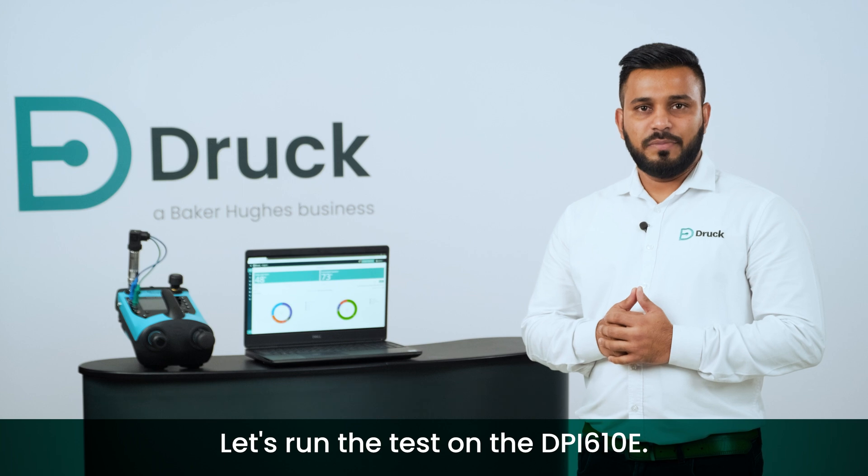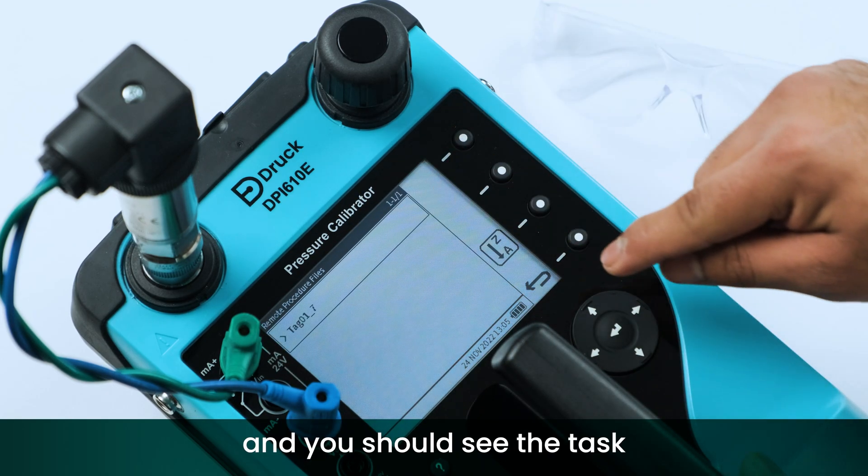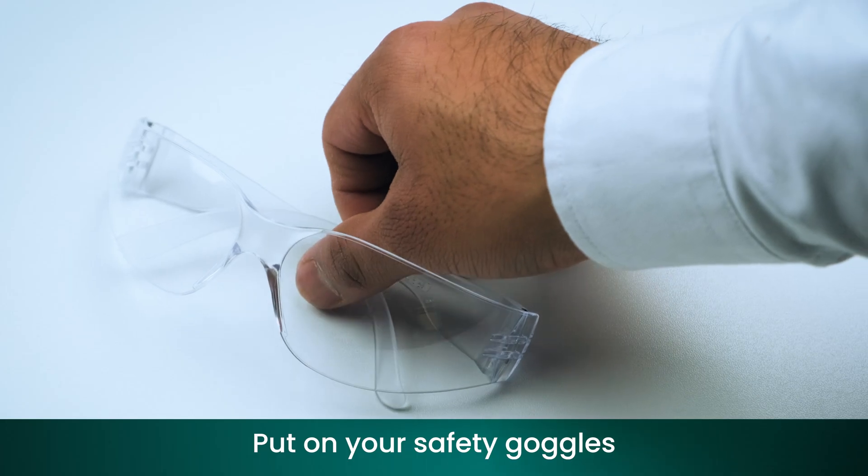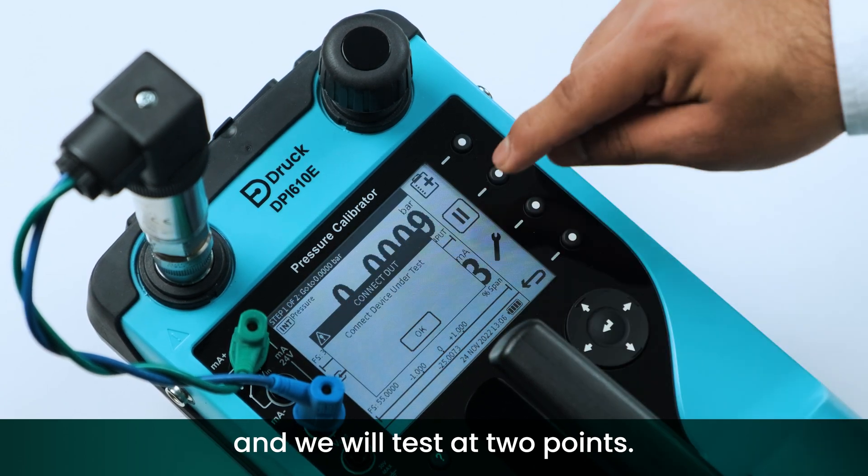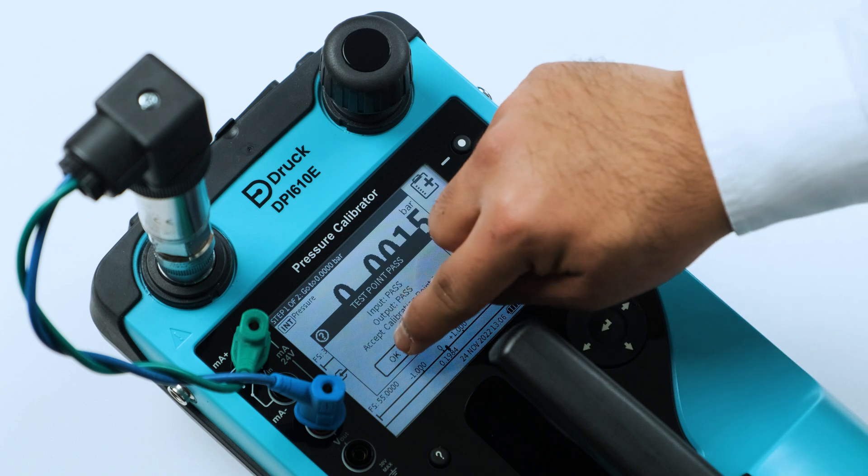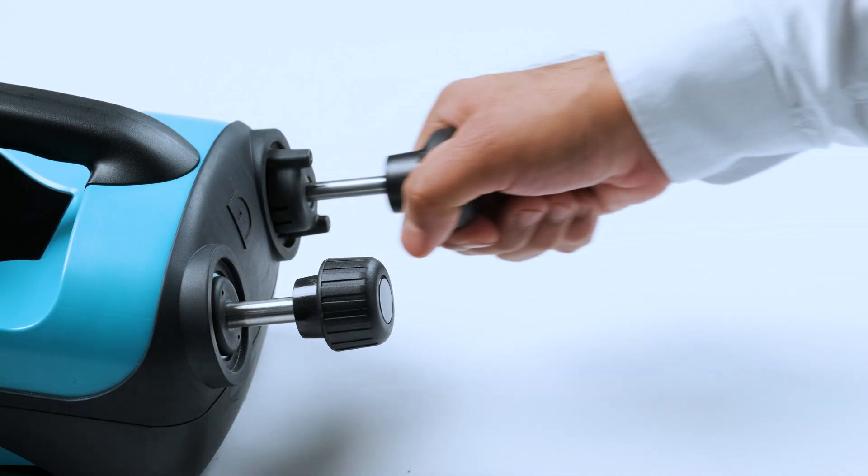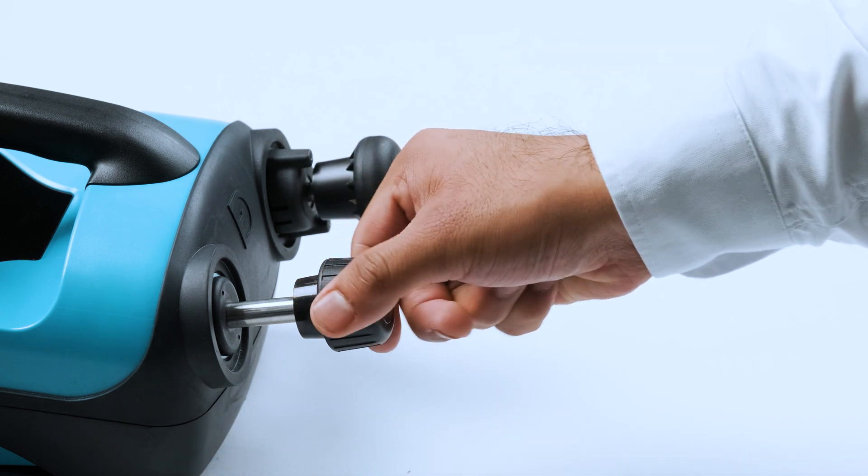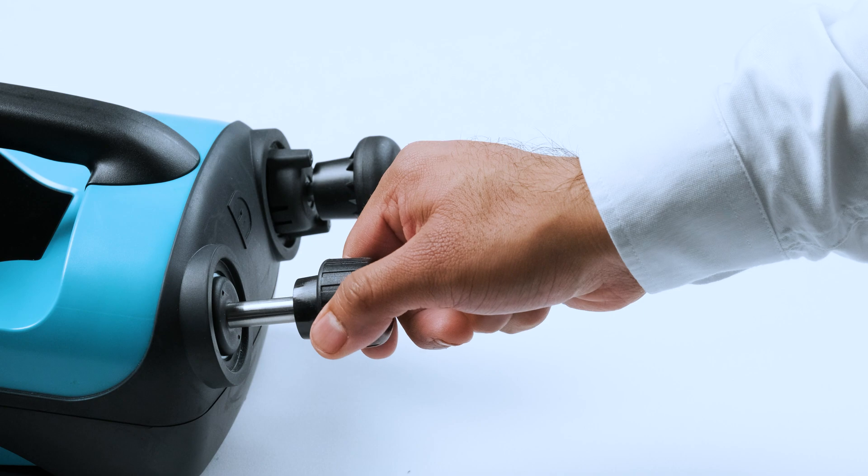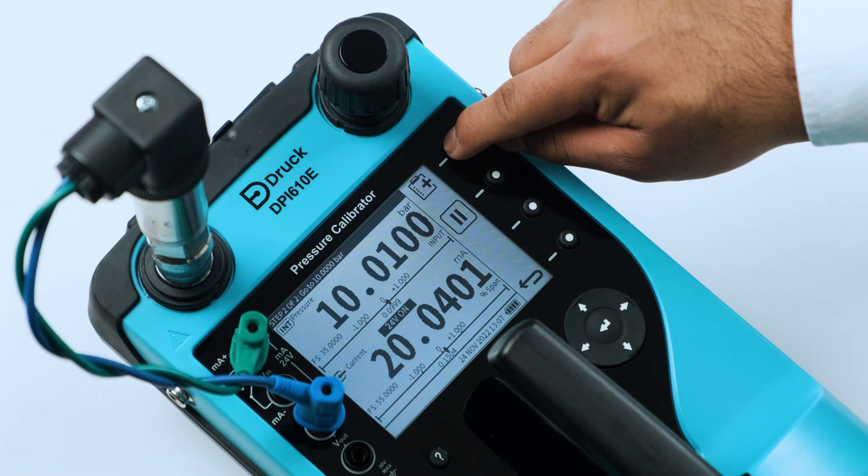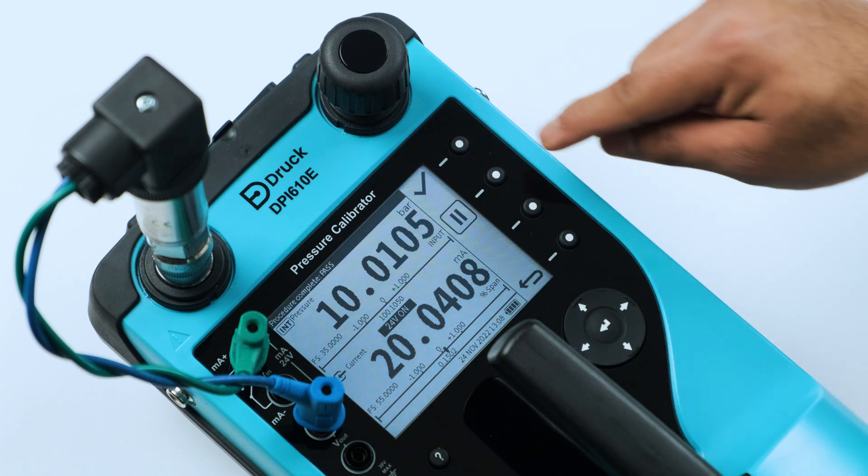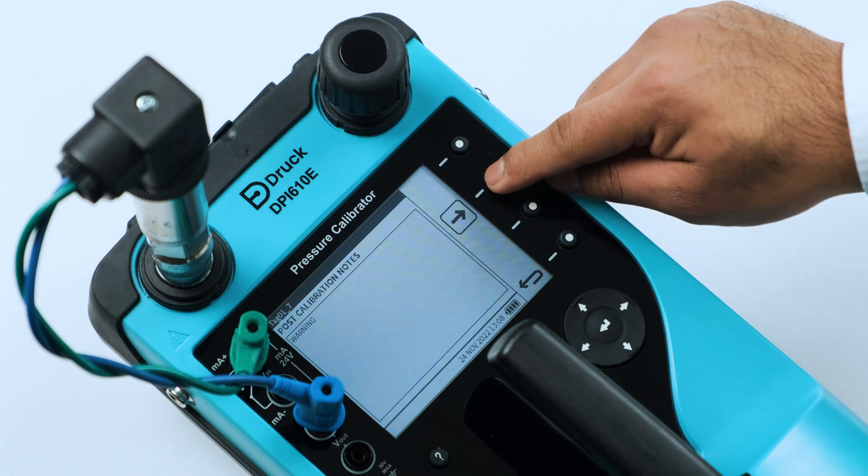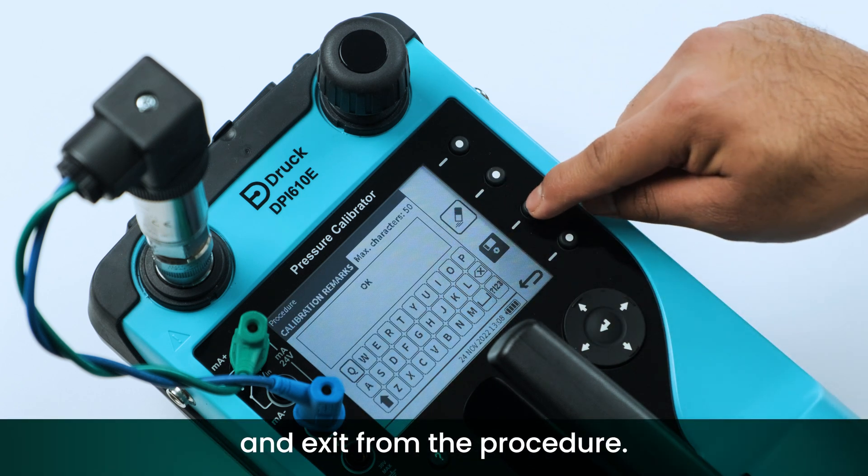Let's run the test on the DPI-610E. Click Documenting, Remote Procedures, and you should see the task that we have just downloaded. Put on your safety goggles and we will test at two points. Save the readings and exit from the procedure.